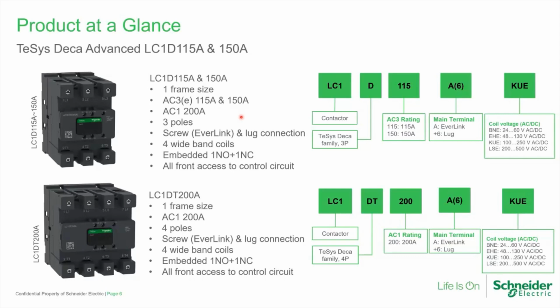This is a 3-pole range, and it will come in 2 types of connections. One will be Everlink connection, and the second will be lug connection. We'll have 4 wideband coils for each rating, and the first range will be from 24 volt to 60 volt, which we'll call the BNE coil. Second, the EHE coil from 48 to 130 volt. These are all AC/DC coils, universal coils. Third one will be KUE, 100 to 250 volt AC/DC. And the fourth one, LSE, which is from 200 to 500 volt AC/DC.